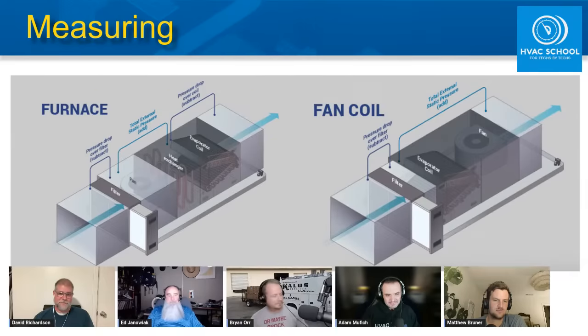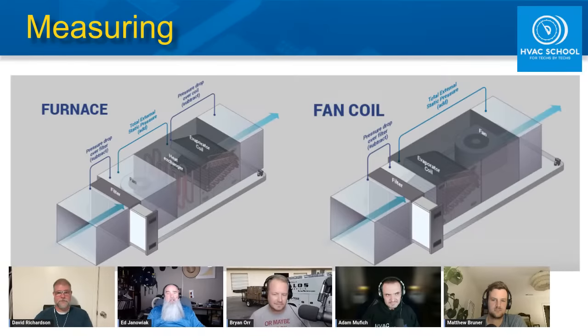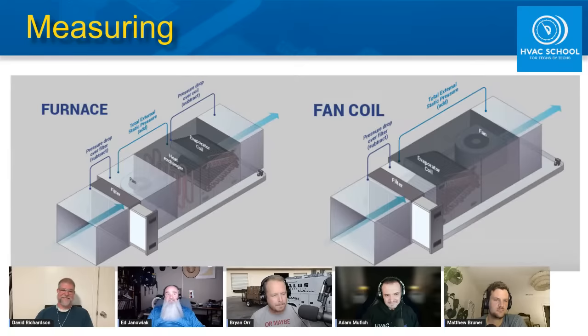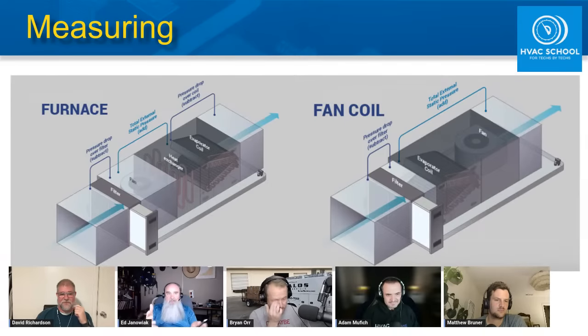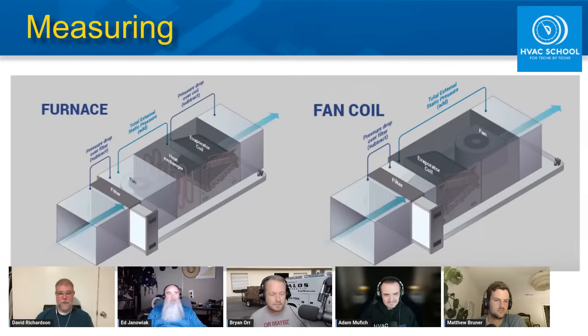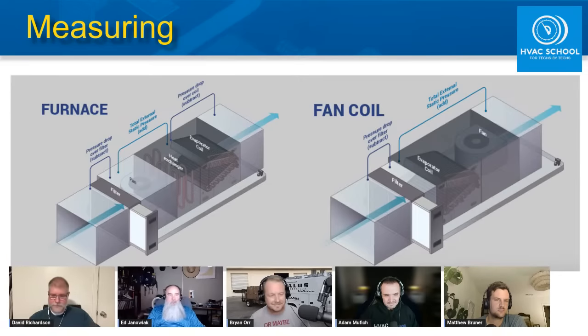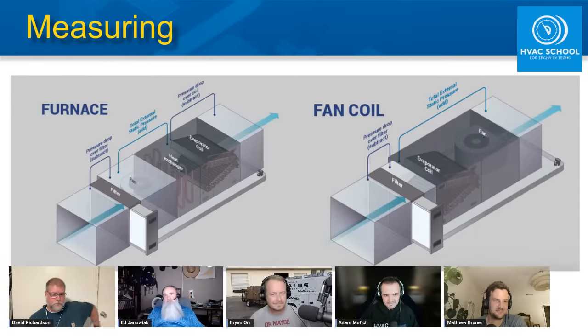Ed's first static pressure reading with someone who actually knew what they were doing was with a DG2 — predecessor to the DG3. The number was 100 pascals, before digital manometers had inches of water column. The principle was simple: if you had 100 pascals on the supply, it was your problem; 100 pascals on the return, it was your problem. You would hopefully come up with something more favorable when doing your full external static pressure measurement, and later it all started to make sense.